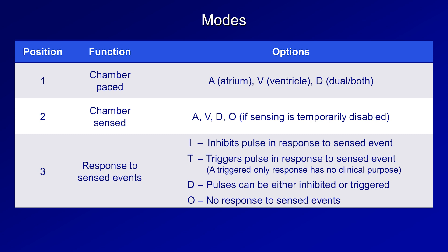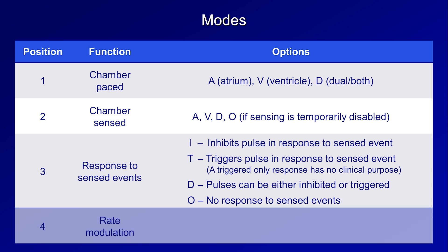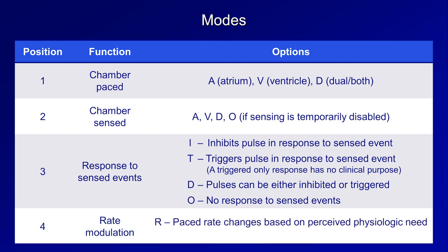When used, the fourth position indicates whether or not there is rate modulation available. An R means that the paced rate changes based on perceived physiologic need. The most common way for a pacemaker to determine this is via an accelerometer within the generator, which interprets repetitive physical motion as an indicator that the person is walking quickly, jogging, or swimming.